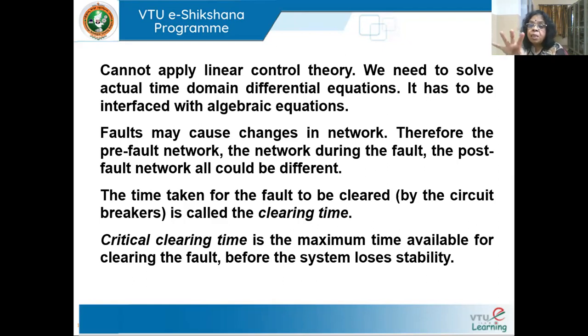Now, I told you we use this for planning. So how do I plan or design? I design the system to withstand the worst fault. So you see different faults, and what is the critical clearing time for each of them? And you take the worst case, that means the shortest time.